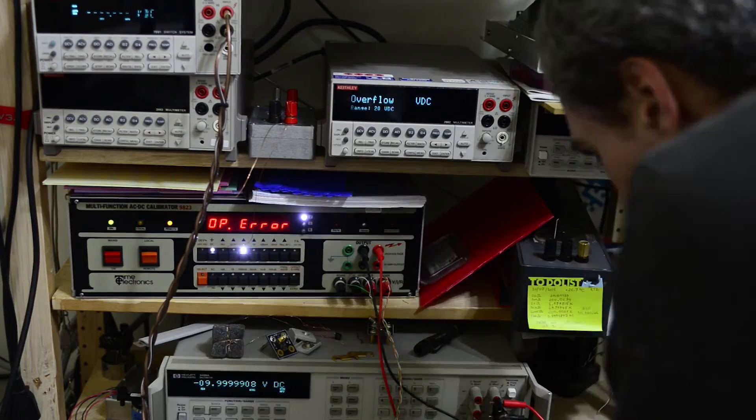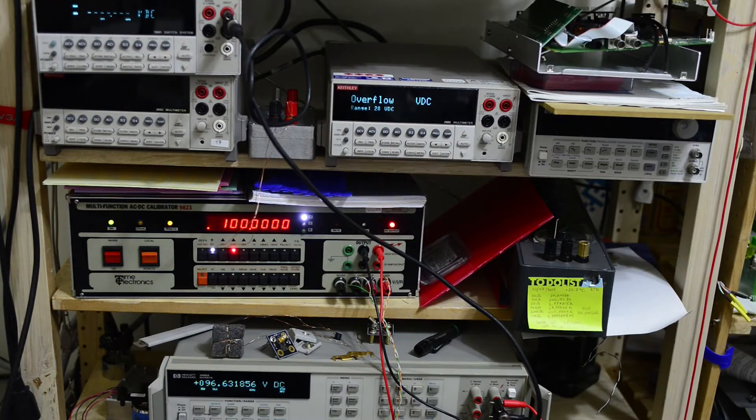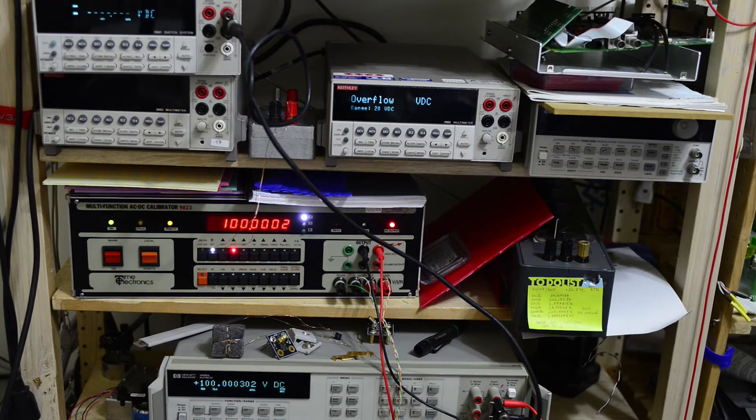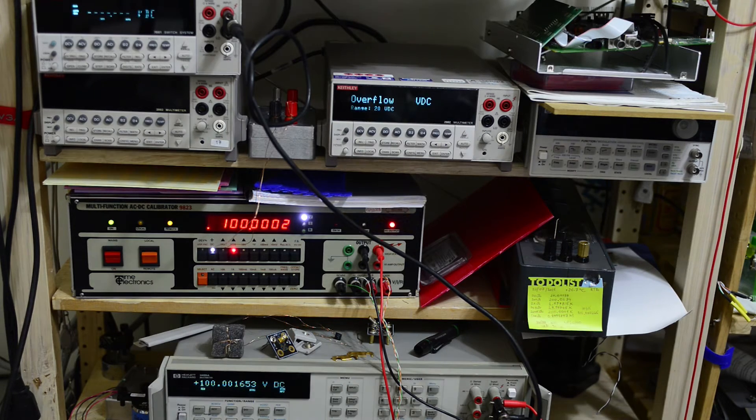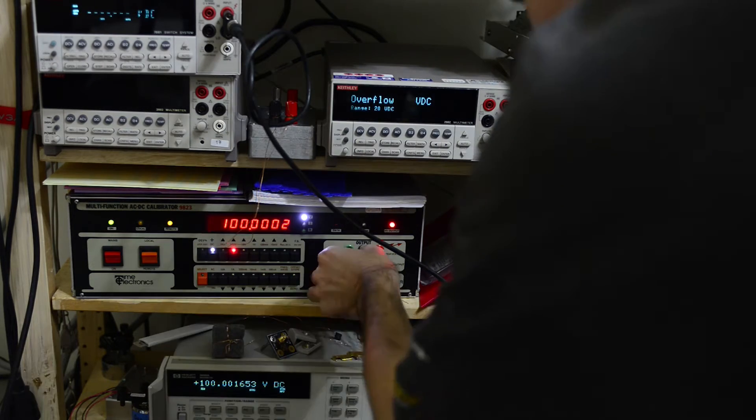Now I will switch to high voltage terminals and use 100 volts to source. This step finishes quickly.